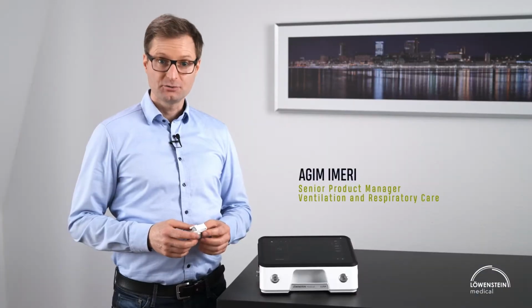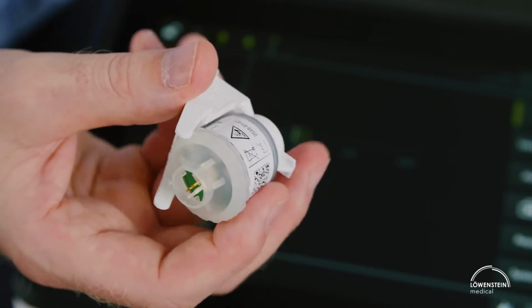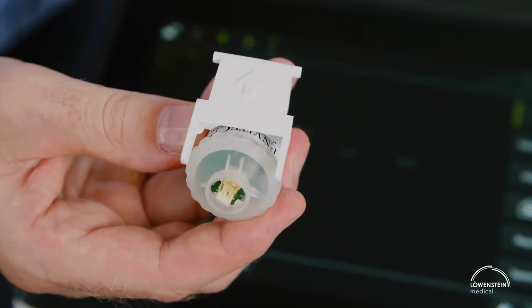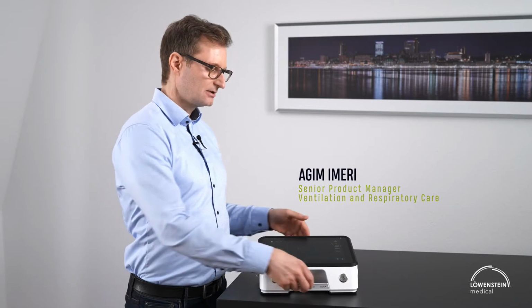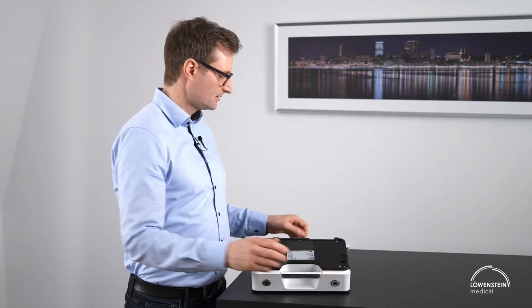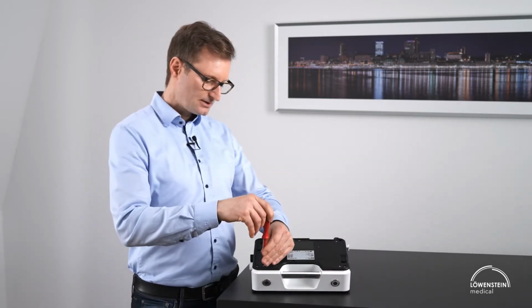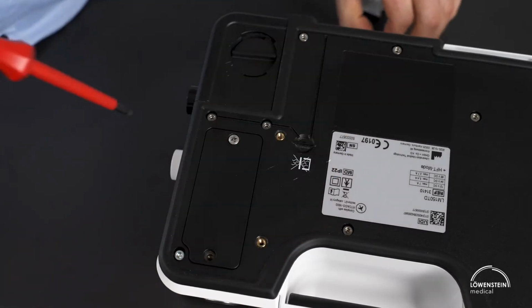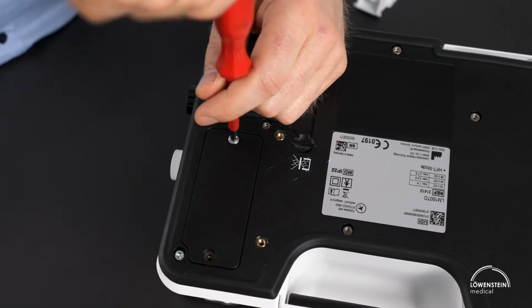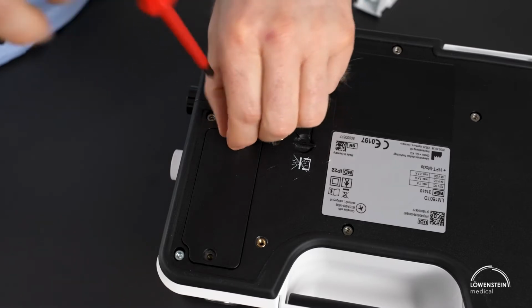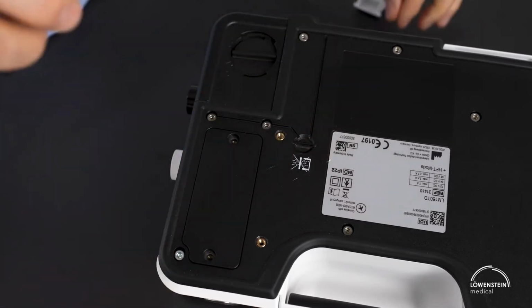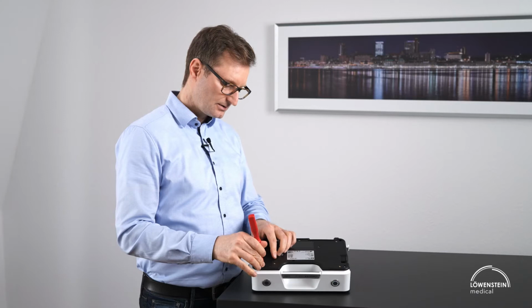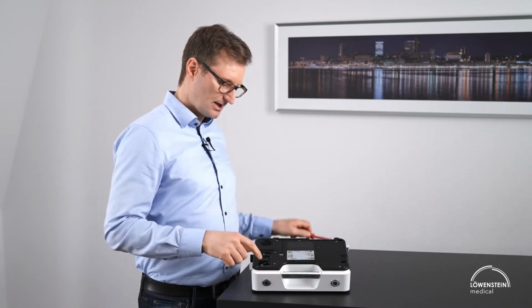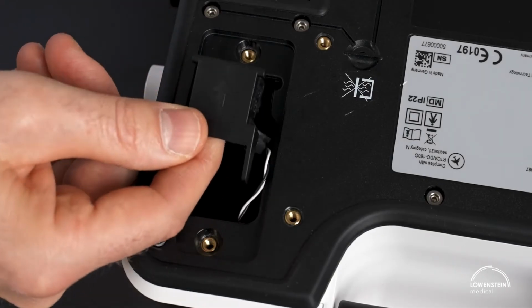To measure the FiO2, first we need to insert the FiO2 cell. To insert the FiO2 cell, we turn over the device onto the display side and loosen the cover. Inside the device, you will find a black sealing plug.